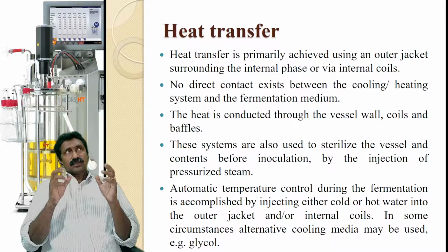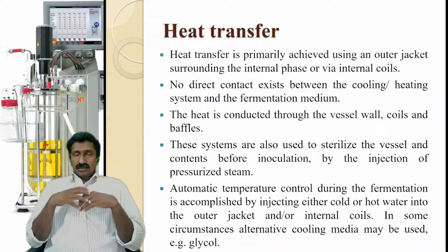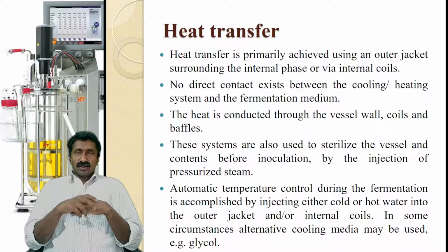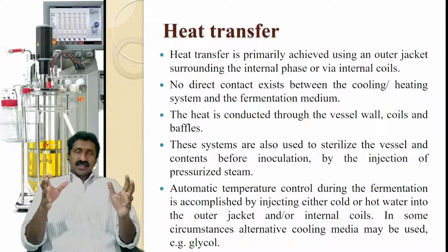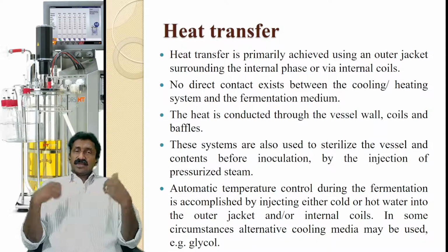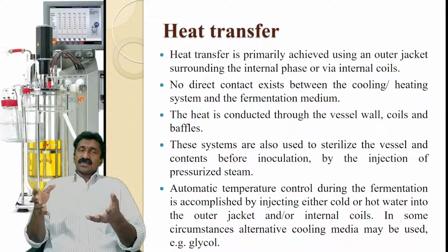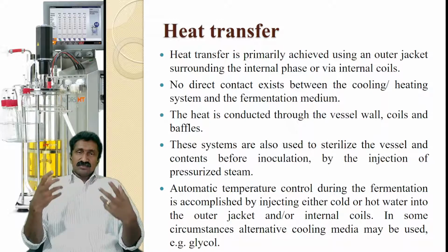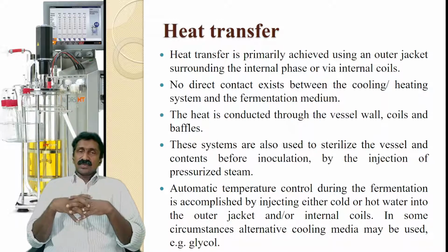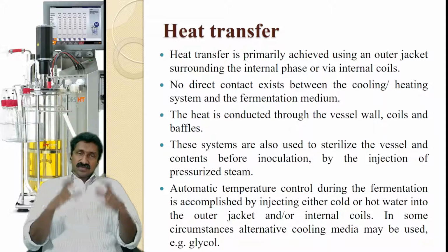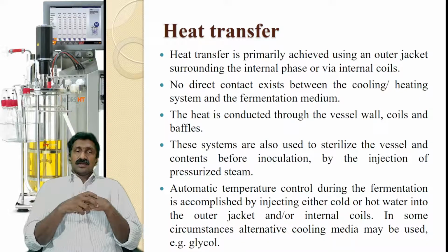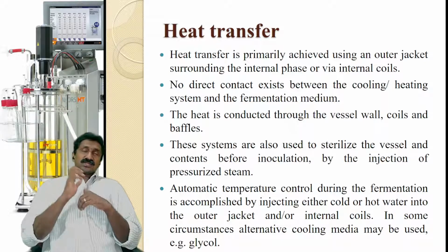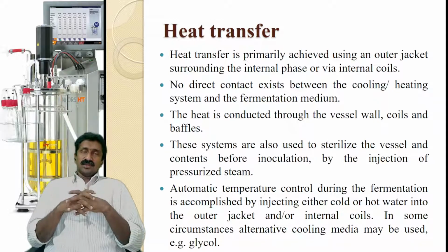So usually the larger vessels, maybe gallons in size, are not filled with externally pre-sterilized medium, and pre-sterilized medium is not transferred into the vessel. Before filling the vessel with the medium, you can sterilize the entire vessel and tubings with pressurized steam. And again, after filling the medium, the entire medium can be heated within the vessel itself, so that transport of the medium into the vessel after sterilization can be avoided, which also invites contamination.